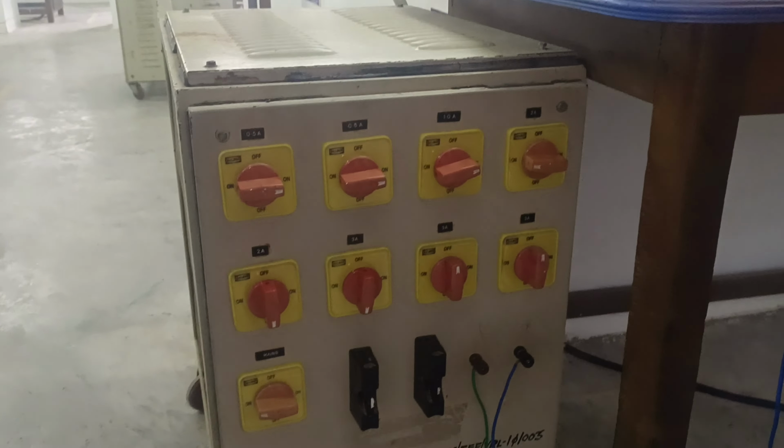You see here the load current is getting increased, then the voltage is getting down, and the field current is also getting down. Now it is connected in the differential mode. Again, it is 2 ampere, and you can apply the load. Now it is 4 ampere. As the load current increases, the generated voltage is getting down, and the ammeter reading, that is the field current, is also getting down. Likewise, up to 10 ampere you can increase the load and note all the readings.